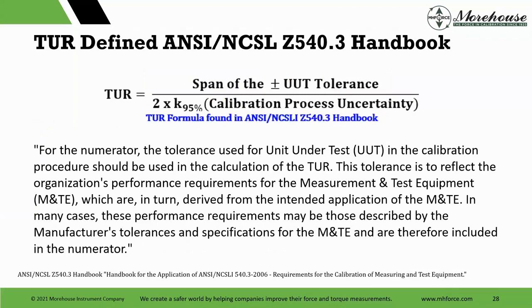But if we look at decision rules and we look at definitions, and I've talked about this before, ANSI Z540 basically says for the numerator, the tolerance used for the unit under test and the calibration should be used in the calculation of TUR. The tolerances reflect the organization's performance requirements for the measurement and test equipment, and it goes on.